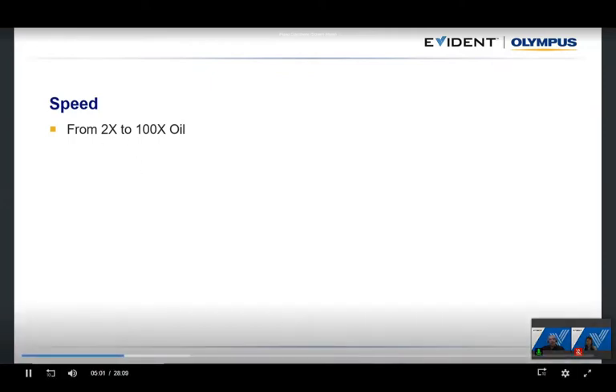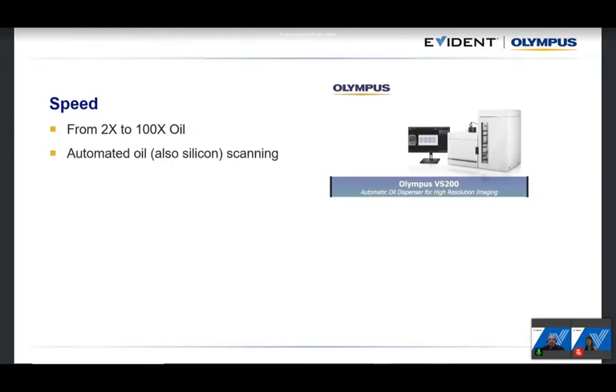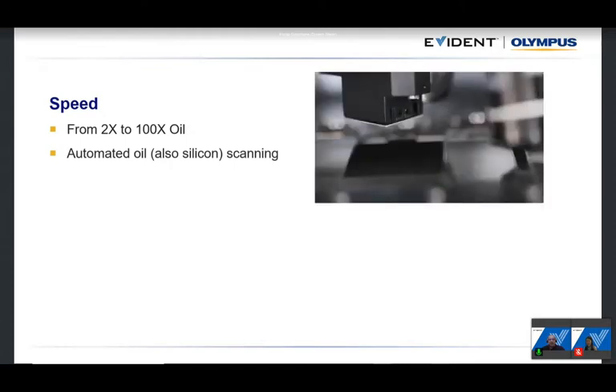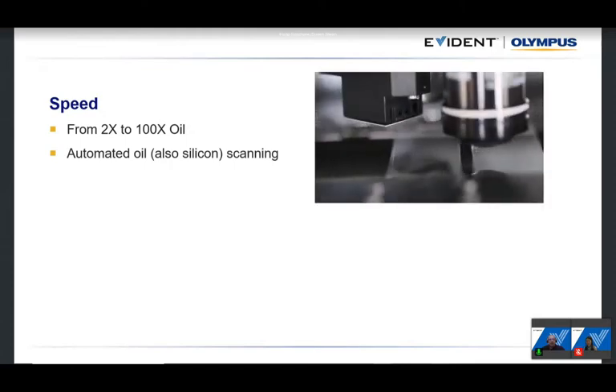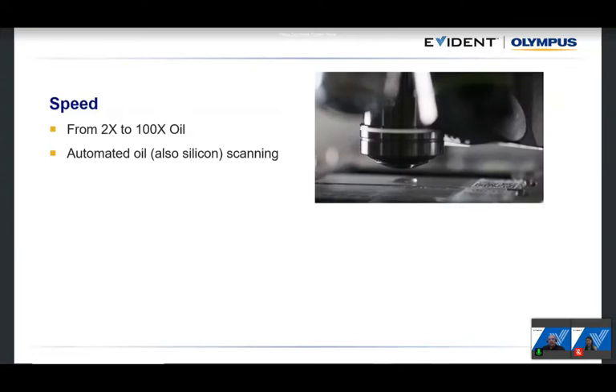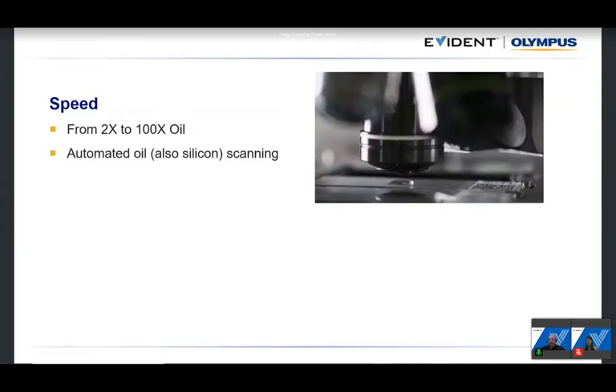Speaking of speed: the system uses standard objectives with six positions, and in each position you can mount any objective from 2x up to 100x oil magnification. This means you can always find the best compromise between detail and scan speed. For 100x oil, we have automated oil management — the system calculates the necessary quantity of oil and drops it automatically onto the slide so oil scanning starts fully automated.